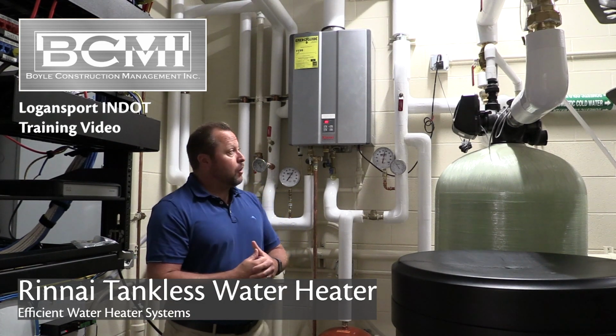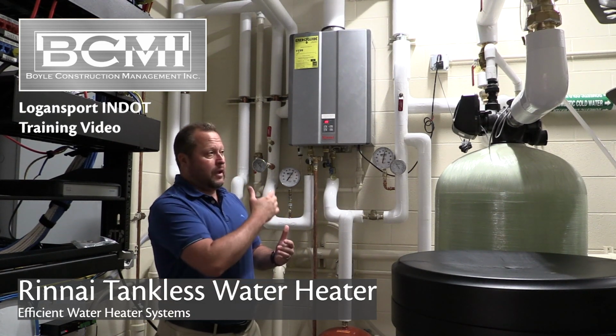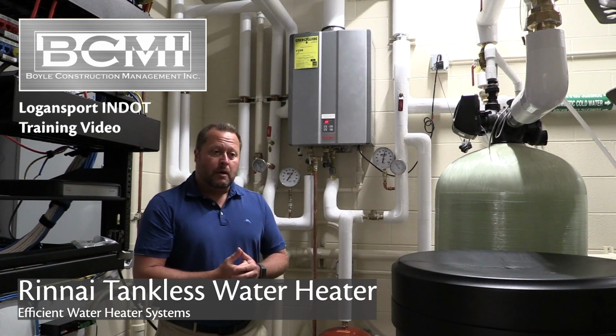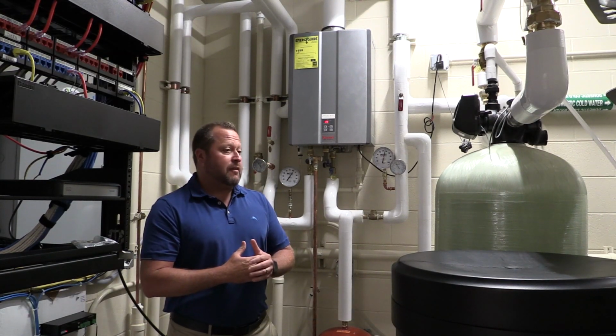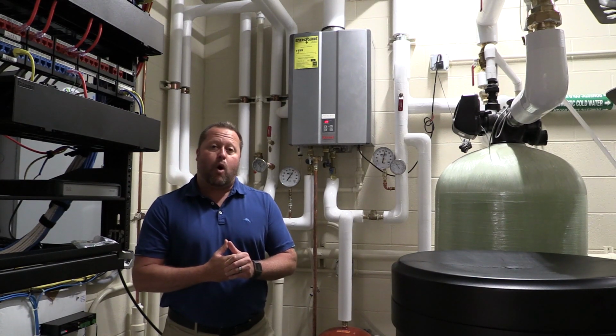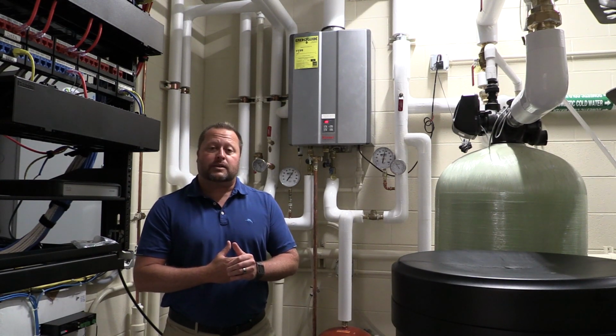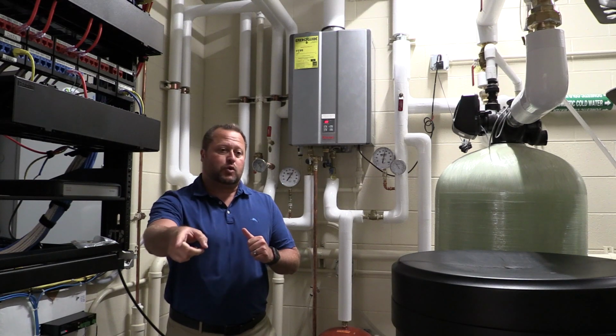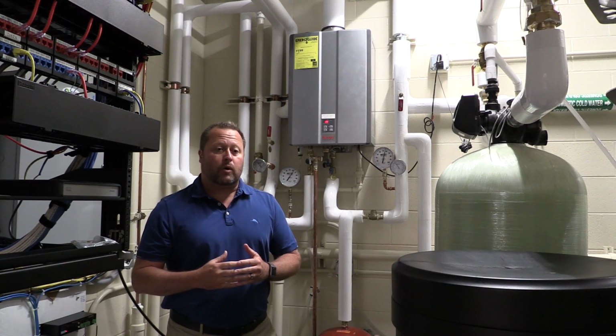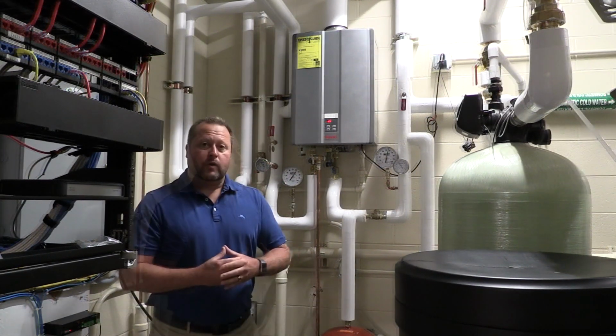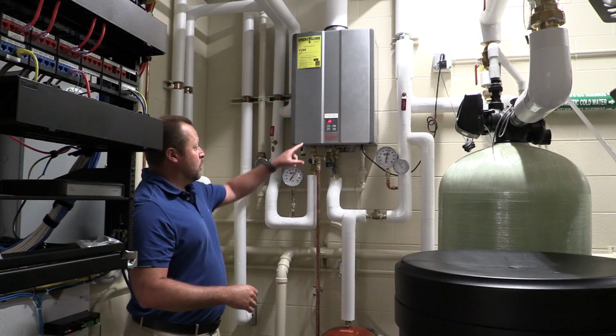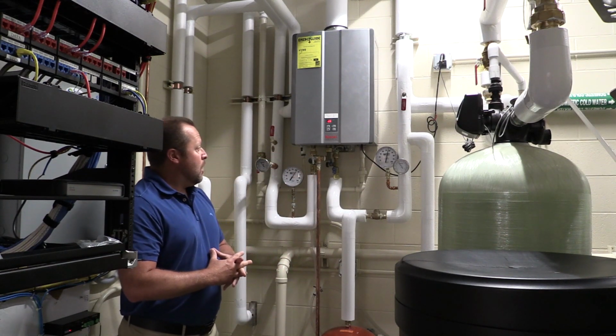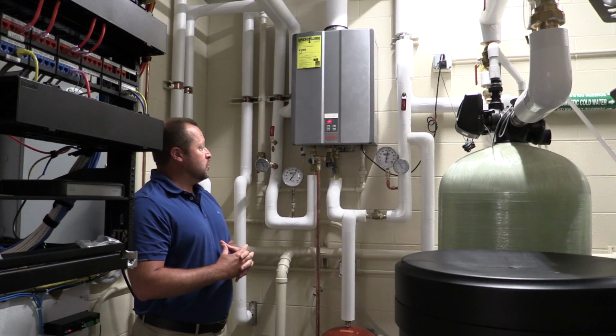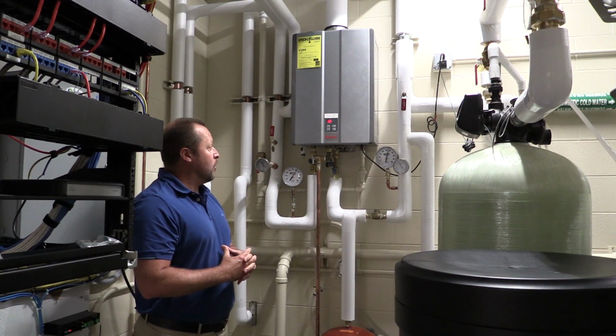And I'm here to talk about our RU199IN today, tankless water heater by Rinnai. It's been placed in this INDOT facility for the domestic water for a sink. That's one sink that it's sourcing water to and keeping water hot in that sink. Currently the temperature is set for 120 degrees, which you see on the panel here. Temperature can be increased or decreased by pushing the up or down arrows.